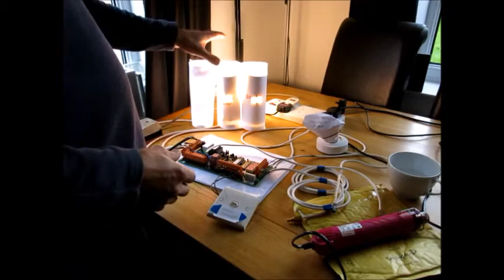But if I warm this up again now, simulating the boiler warming the heat store up, once it gets up to about 75 again, this will kick back into the central heating. There we go, it's back in. Oh, it's actually about 60 odd. But there you go, you'll see, and if I turn that off again.